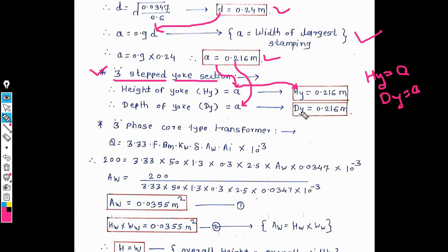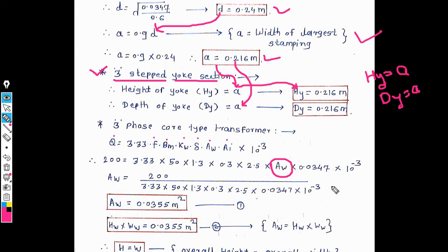The output equation for the three-phase core-type transformer is: Q = 3.33 × f × Bm × Kw × sigma × Aw × Ai × 10⁻³, where Q is rating, f is frequency, Bm is maximum flux density, Kw is window space factor, sigma is current density, Aw is area of window, and Ai is net iron area. Substituting all known values and rearranging for Aw gives Aw = 0.0355 m².